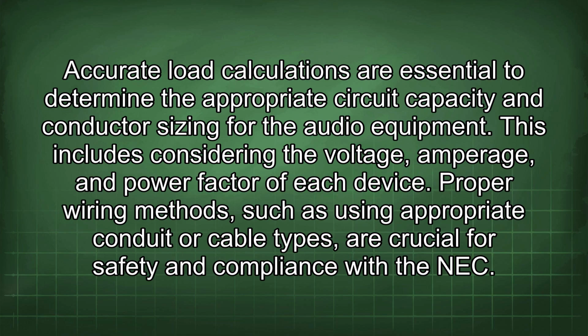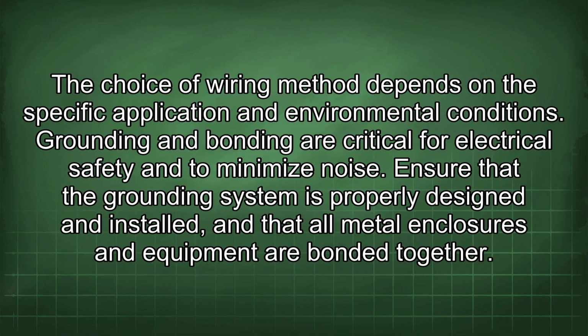Proper wiring methods, such as using appropriate conduit or cable types, are crucial for safety and compliance with the NEC. The choice of wiring method depends on the specific application and environmental conditions. Grounding and bonding are critical for electrical safety and to minimize noise. Ensure that the grounding system is properly designed and installed, and that all metal enclosures and equipment are bonded together.